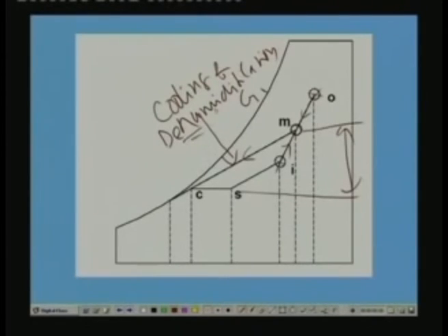So, that is achieved in this process, but you find that this point does not lie on the RSHF line. This RSHF will be quite low because of the high latent load, let us say less than 0.6. Since this point does not lie on this line, if you leave air at this condition to the conditioned space, it cannot take the required amount of sensible and latent heat loads. So somehow you have to bring this point onto the room sensible heat factor line.